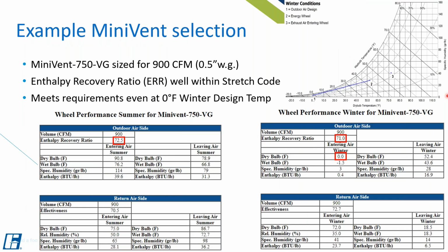The mini vent 750 Green is sized for 900 CFM and 0.5 inches water gauge. And granted, that 0.5 inches of water gauge is, in this case, low. I should have honestly selected it for more, but this is just a really good example of how we can select. It's funny, it says 750 in the name of the unit, but obviously this is sized for 900 CFM, which is the high limit, and we can already get the enthalpy recovery ratio in the conditions required. So at 0 degrees dry bulb, outdoor air, we can still get the above 70% enthalpy recovery ratio needed. And this is at a very economical, cost-effective option.